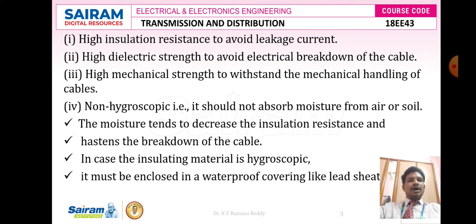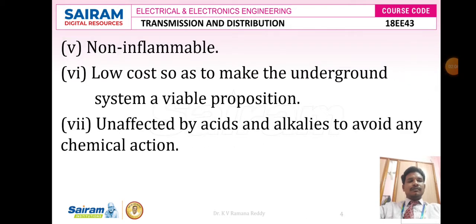The material should be non-hygroscopic, meaning it should not absorb moisture from air or soil, as moisture tends to decrease the insulation resistance and hastens the breakdown of the cable. In case the insulating material is hygroscopic, it must be enclosed in a waterproof covering like a lead sheath. It should be non-inflammable, low cost to make the underground system a viable proposition, and unaffected by acids and alkalis to avoid any chemical action.